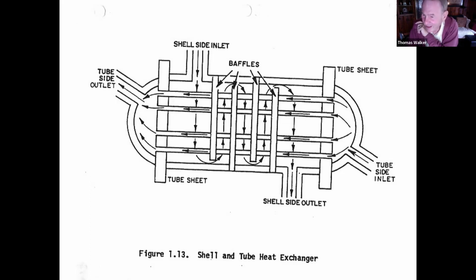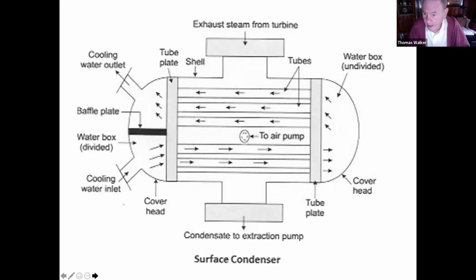Plants have many shell and tube heat exchangers. This is also how we heat up fuel oil. We'll have fuel oil inside the tubes and steam outside. You get the idea. So when they ask you, can you give us an example of a closed feed water heater? The shell and tube heat exchanger is the most common. They'll often ask third engineers, can you name 2 types of closed feed water heaters?